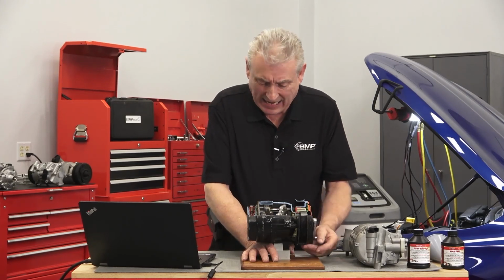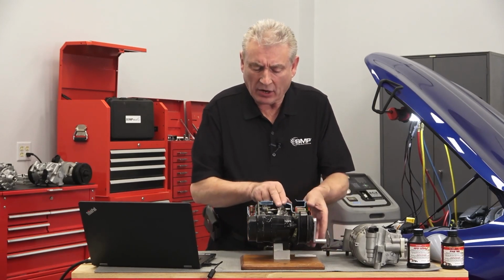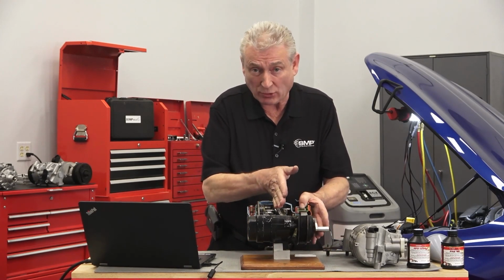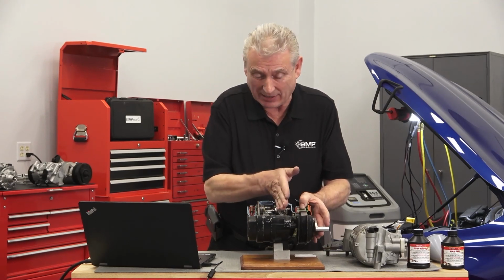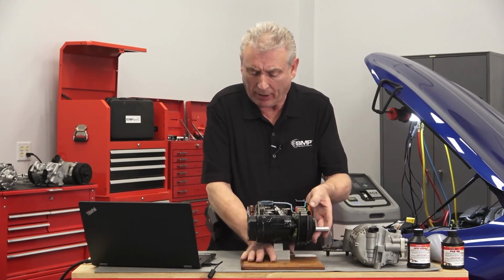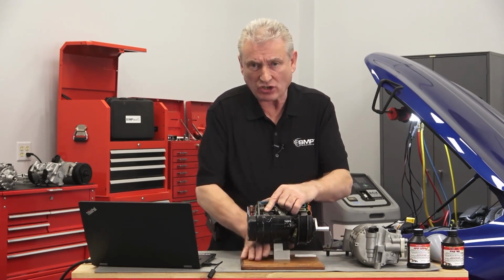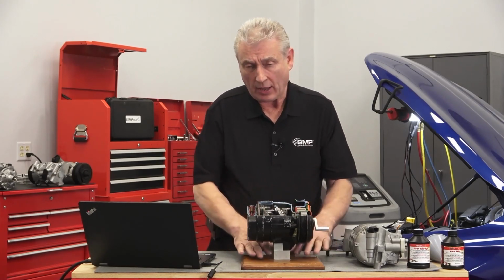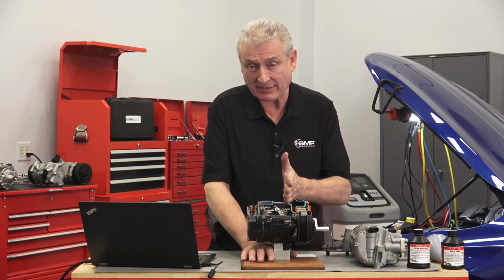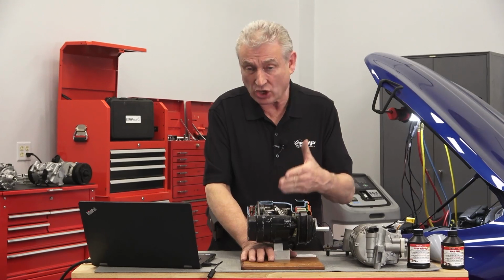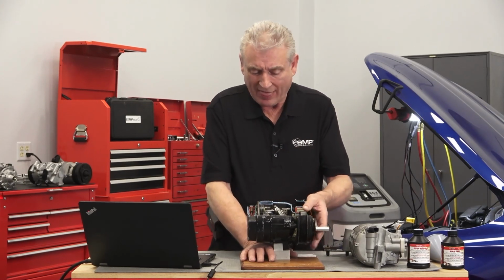So the whole idea here is, if I can control the angle of this swash plate gradually, smoothly, seamlessly on the fly as the compressor is working, I can change the pumping output of the compressor gradually as the heat load demand changes on the system. So that's the basic idea.